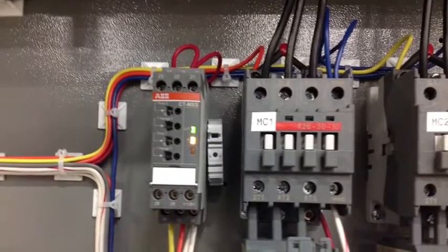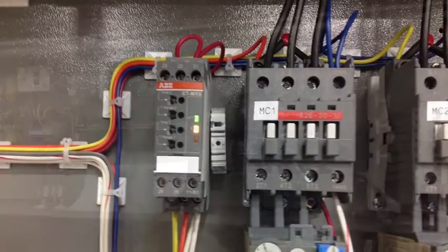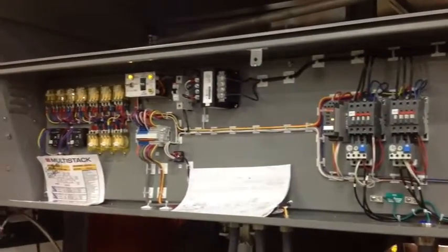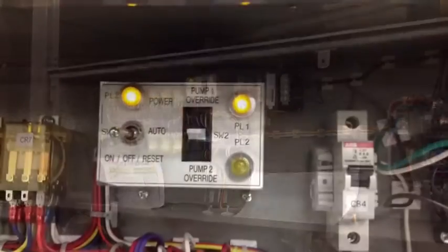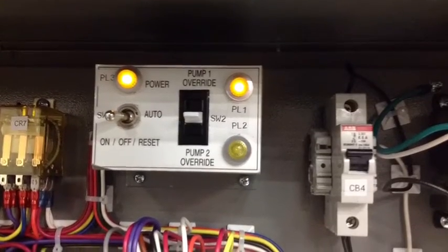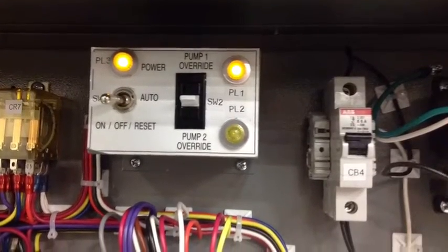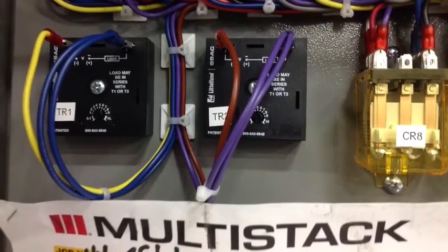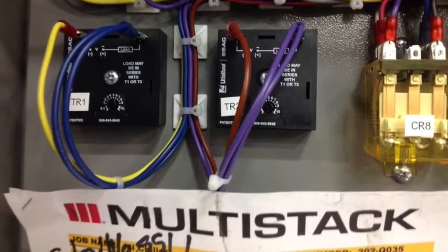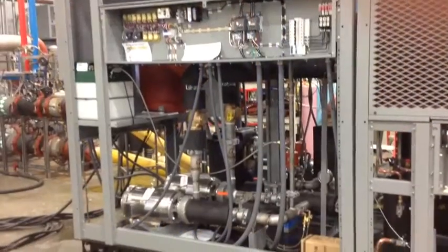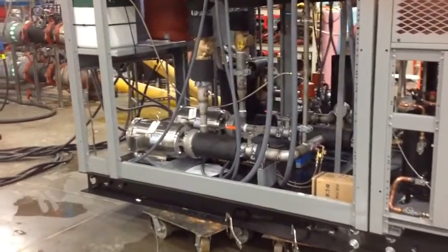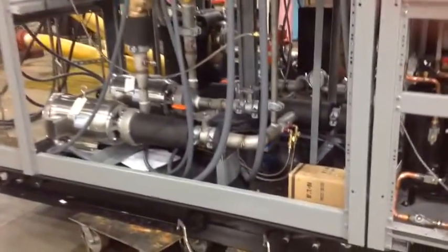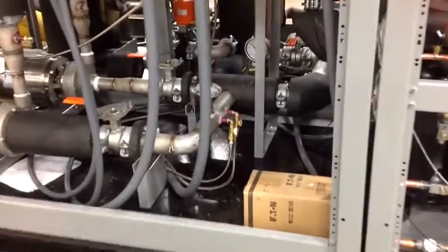The contactors for the pump, this is a close-up of the ABB timer, which rotates lead lag pump operation. The on-off reset and placing pump 1 or pump 2 in lead switch. And these 2 timers are used with our DP switch to allow 5 seconds, as they are currently set up, for the DP to be proved.